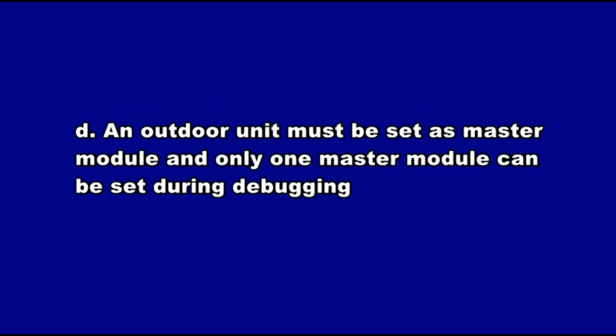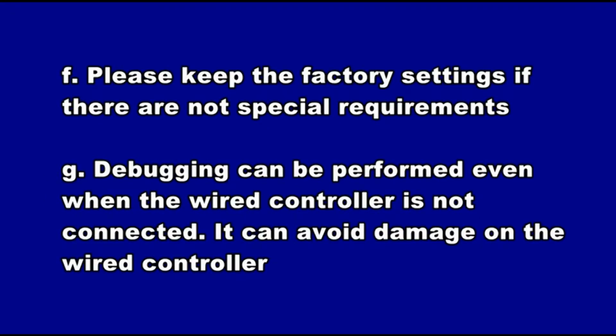An outdoor unit must be set as master module, and only one master module can be set during debugging. An indoor unit must be set to master indoor unit, and only one can be set during debugging. Please keep the factory settings if there are no special requirements. Debugging can be performed even when the wired controller is not connected. It can avoid damage to the wired controller.